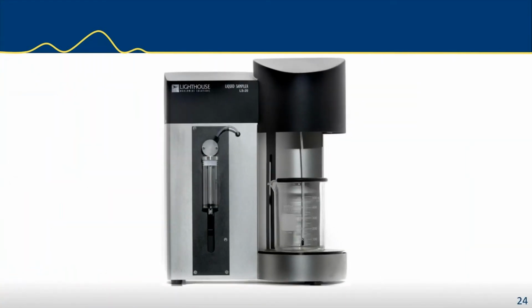If you're wondering how the sample gets through the sensor, I did talk about the syringe and the action of that syringe pulls it through. Here we see the syringe mechanism. The syringe is used to ensure an accurate sample volume is taken. The sample is pulled through the sensor, as we saw, and with this system, specific volumes can be programmed into the liquid particle counter software based on the size of the syringe, and you can get larger syringes, and that ensures repeatable and accurate volumes taken. Because volume is really important, that's a segue into our next slide. We'll look at these volumes.